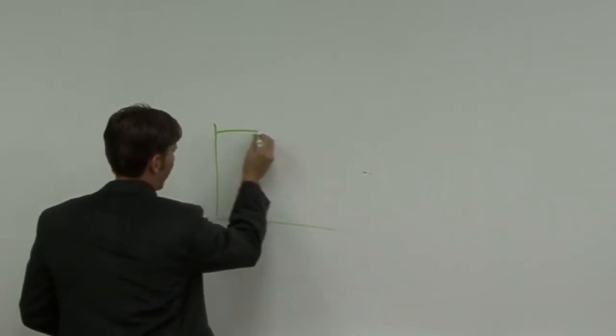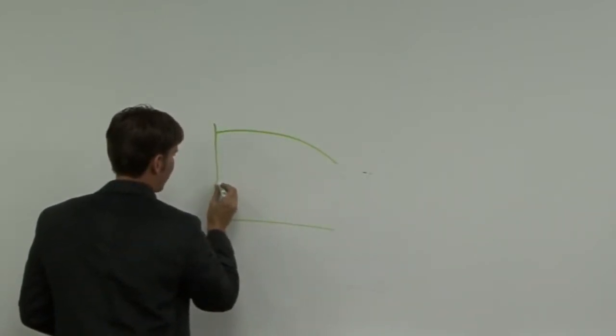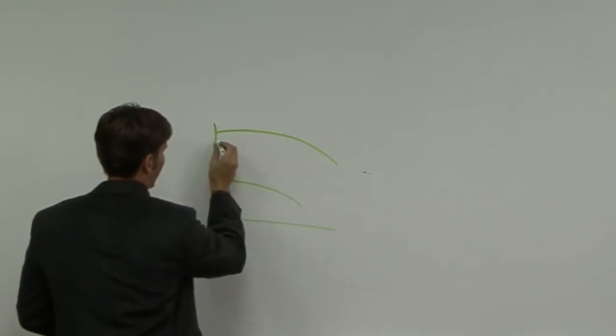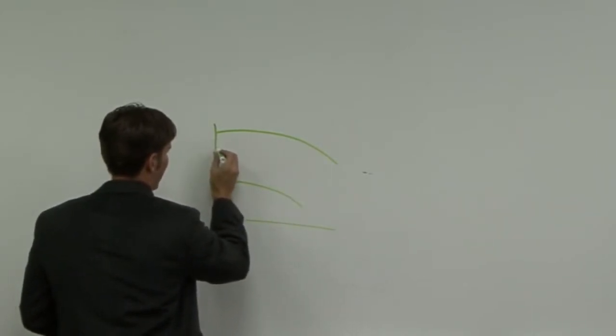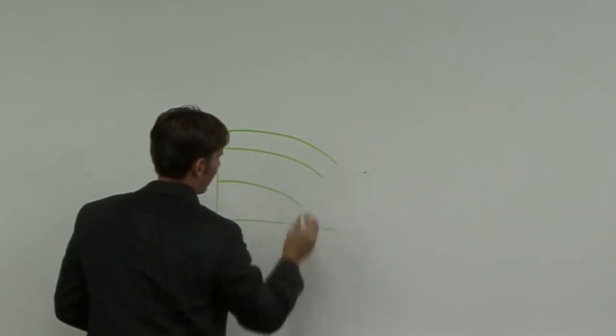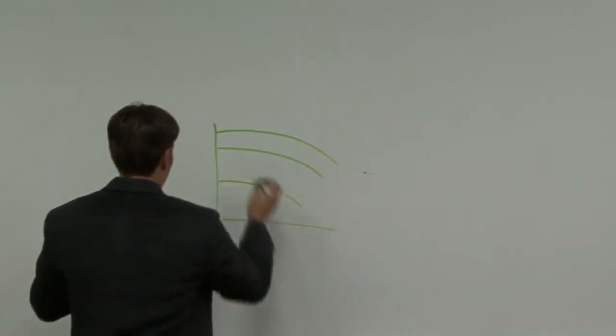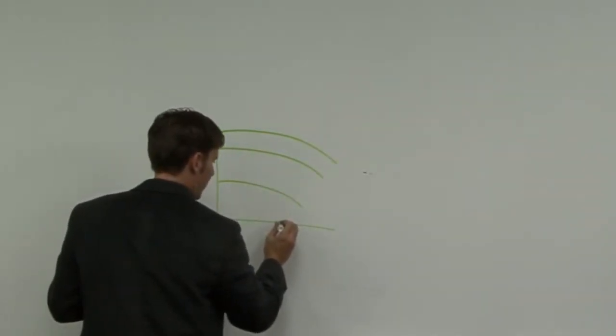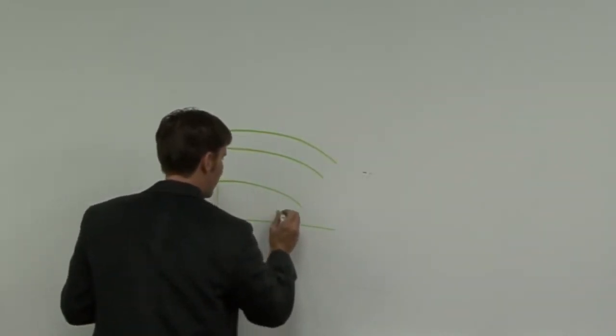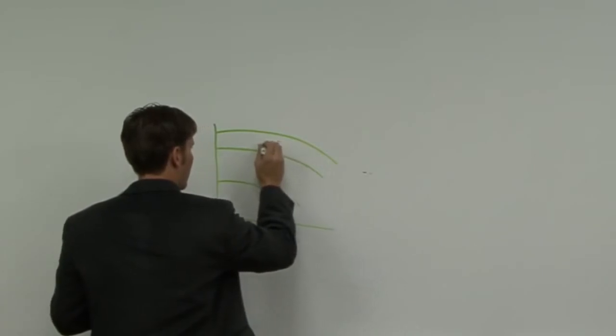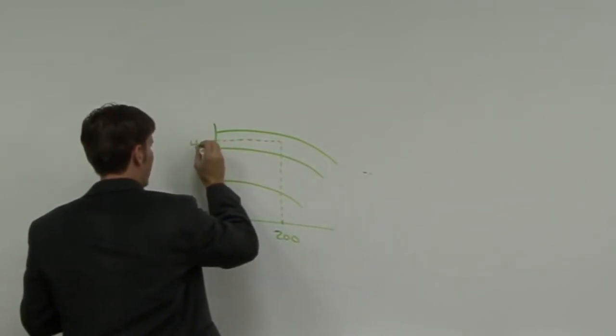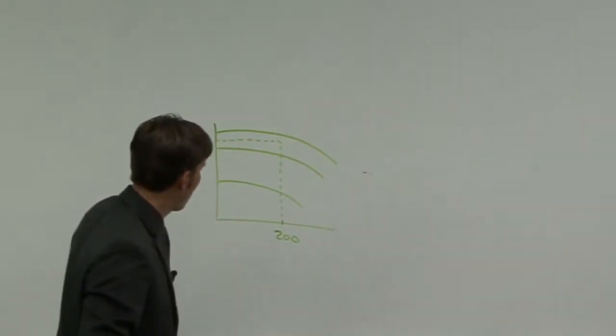This is the 7 1/4. This is my 4 3/4, and this was my 5 and I believe it was 5 7/8. Yep, 5 7/8. And we're sitting here at 200 gallons per minute at 40 feet of head.